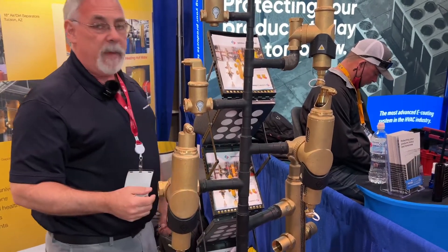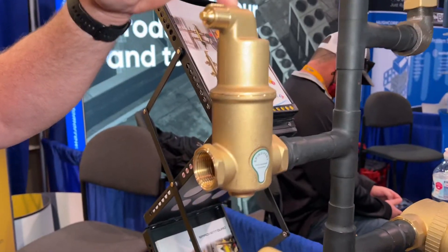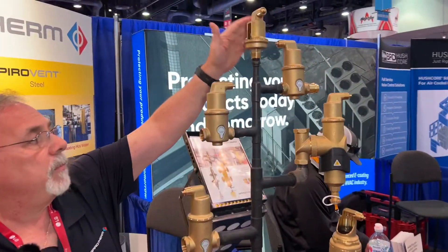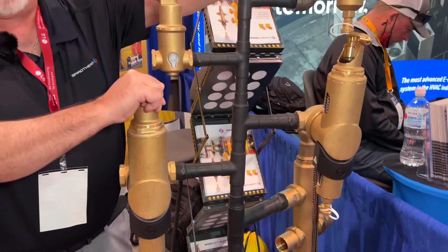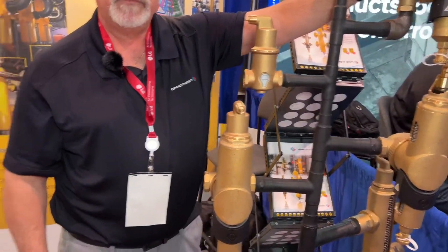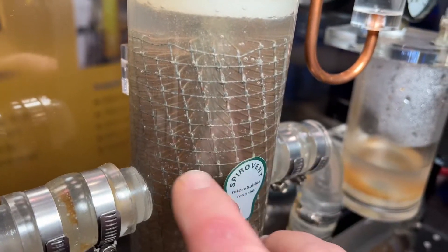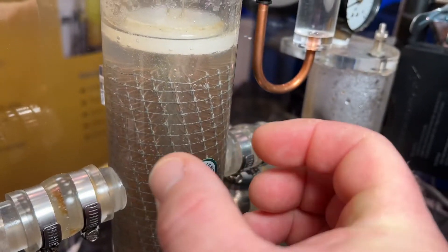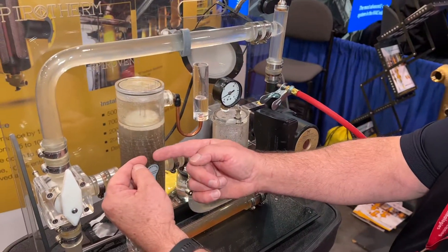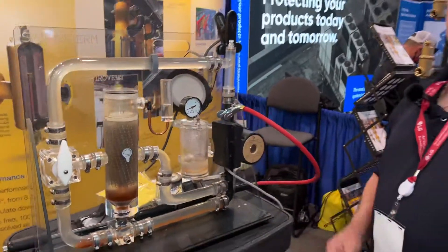The staple of the industry is the Spirovent Junior. One thing people don't realize is that all of the tops on all of these brass units are replaceable — it's the same head. The Spirotop, Spiravent Junior, Combi Mag, and Quads all use the same top and they're all replaceable, so you can just order one and keep it on the service van to cover all of these units. I like this display to show that separation and the air clinging to the media — it's pretty impressive how those bubbles cling to each other, grow larger, and float up to the top. The surface tension causes the bubbles to cling together side by side, they migrate and join together, and once there's enough buoyancy that bubble lifts right off the wire so the air comes straight out.